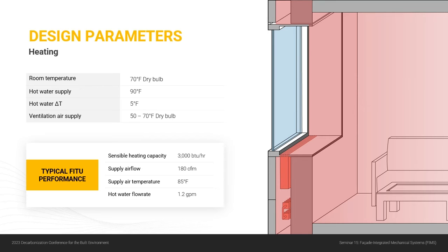Now the ventilation air supply, we'd want to supply somewhere in the 50 to 70 degree range. I like supplying it at 50 because it means, for one thing, in your rooftop unit you might not need any heating at all because your energy recovery alone might be able to get it up to 50. And the other good thing about it is, I mentioned this can be designed as a 2-pipe or a 4-pipe system. If you design it as a 2-pipe system where you're changing over between heating and cooling, when it's cold out, you can go into heating, but you can still get cooling from that ventilation air when you're supplying it at 50. So it's a way of getting simultaneous heating and cooling capacity even when you have a 2-pipe system.